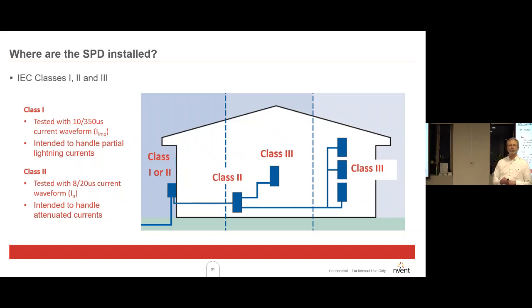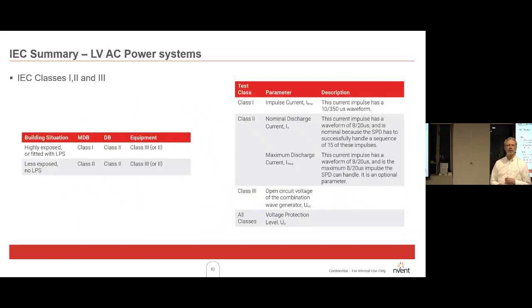Now, these are the classes and where they're used. This is the more detailed information that specifiers will be writing in their specifications. Class 1 or 2 can be used at the point of entry. If you've got direct strike lightning protection on that building and you're following the IEC standard, you'd apply a class 1. If you're following the New Zealand Australia standard, you wouldn't bother calling it class 1. You would just put in a large surge diverter.